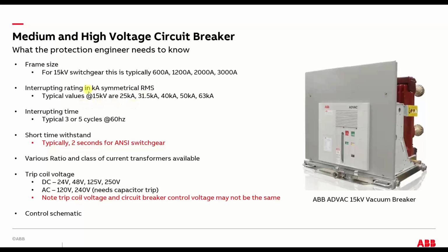The interrupting values are good to know. Now they're all done in kA, just like low voltage. It used to be a different system, but it's changed over the years and got a little bit simpler. Typically, they interrupt in either 3 or 5 cycle. Historically 5 cycle was pretty common, but now I think the 3 cycle breaker is a little bit more common and pretty readily available. This is important because you add this time onto the time it takes for the relay to pick up. And we'll get into that.